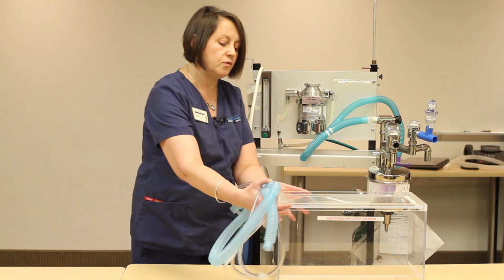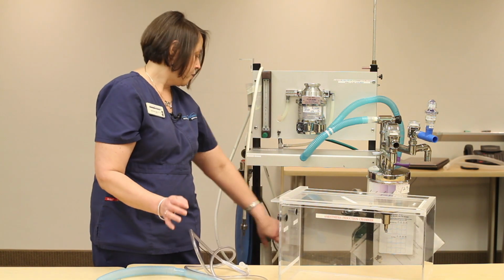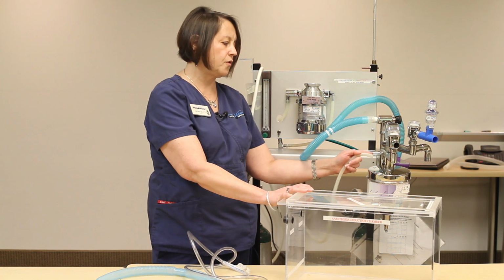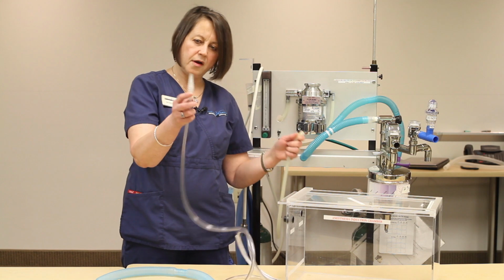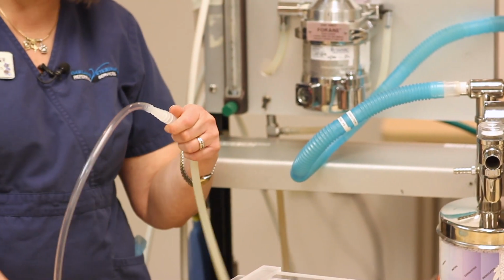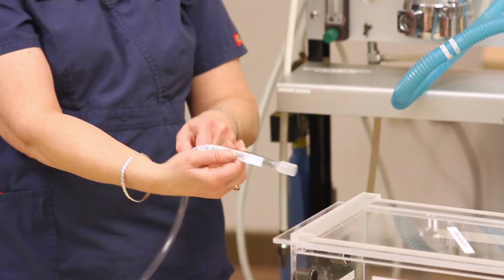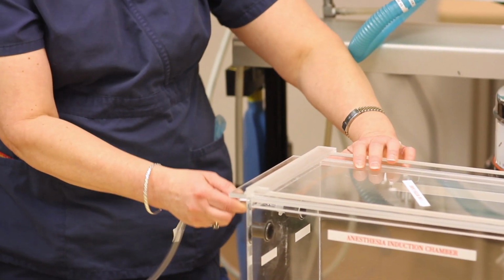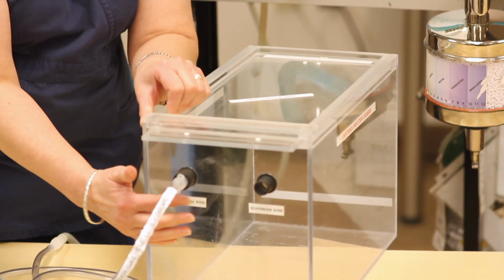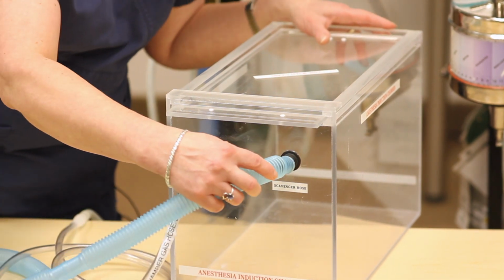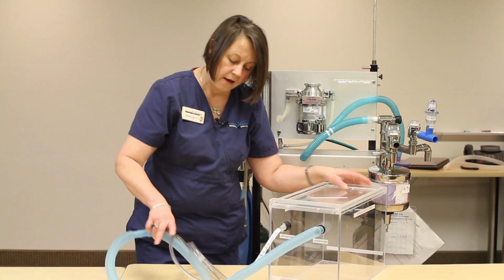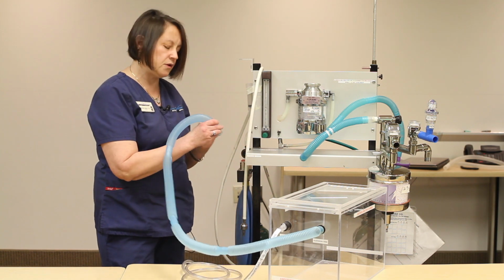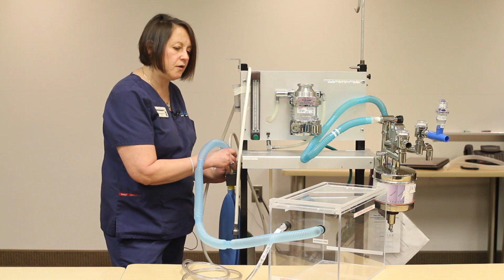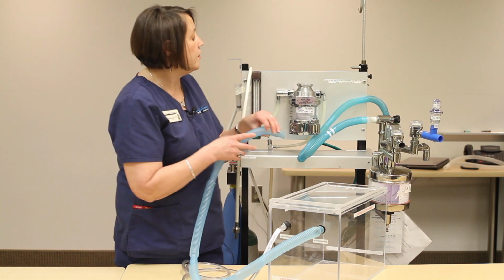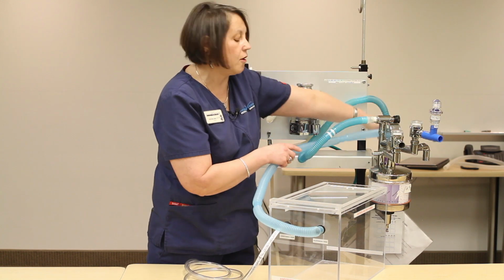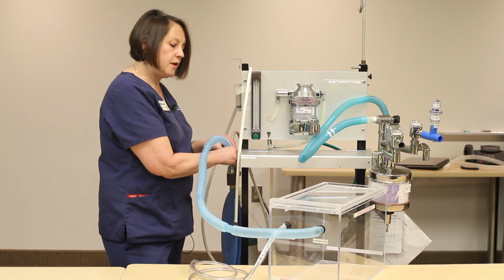And what you're going to do is go ahead and remove the oxygen supply from this location on the EVAD machine. Then you're going to go ahead and hook your Christmas tree into that tube. And you're going to go ahead and insert this hose into this location right here where it says anesthesia hose, and this says scavenger. So we're going to put our scavenger hose right there and make sure that the scavenger hose is either hooked into our active scavenger interface here, or you can certainly use your F-air canister over here. But for this demonstration, we're going to hook it here.